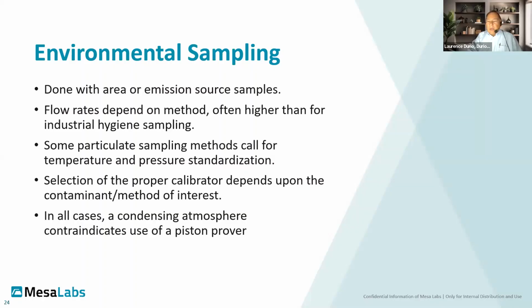In all cases, you cannot use a piston type calibrator in a condensing atmosphere, because you get moisture inside the cylinder and the piston sticks, and generally that will not clear. It's shipped back to the manufacturer for disassembly, clean out, and reassembly. This is particularly the case when you're doing, say, stack sampling, where you've got an awful lot of moisture at high temperature. Sometimes we'll have to do things like put in ice baths to cool that gas flow and condense the moisture out so that we can adequately calibrate and sample. And this is one of the situations where you're actually sampling for particulates in a standardized rather than volumetric method.